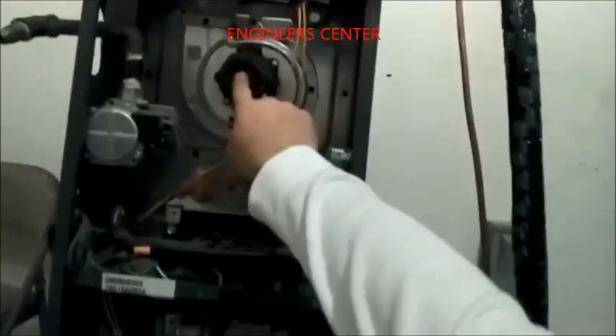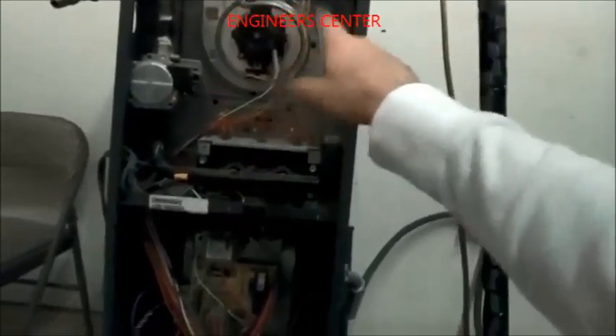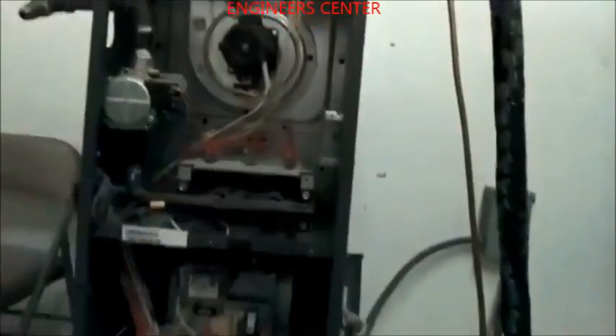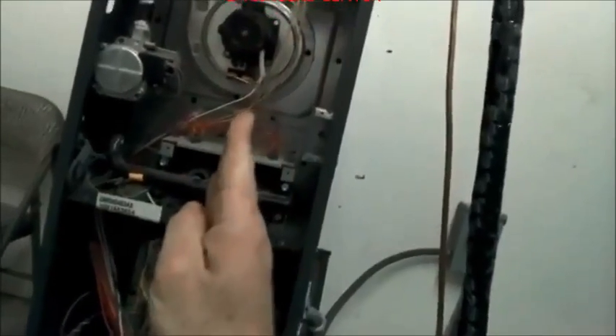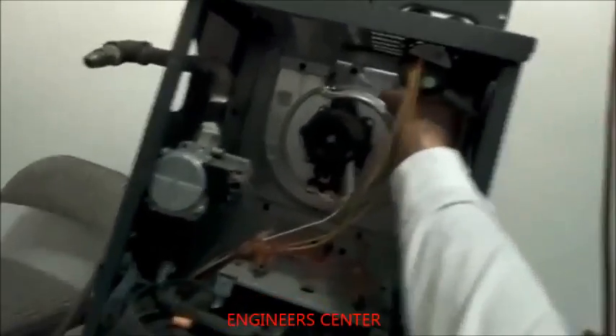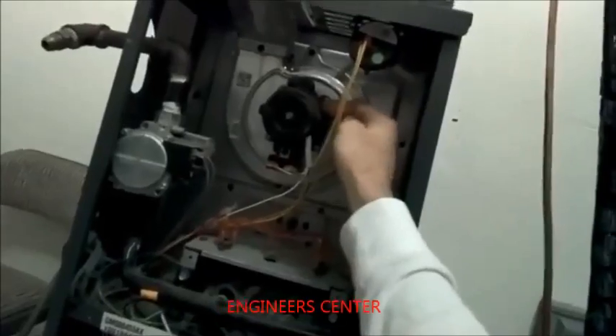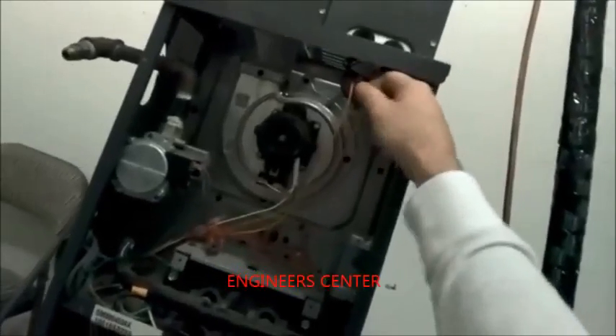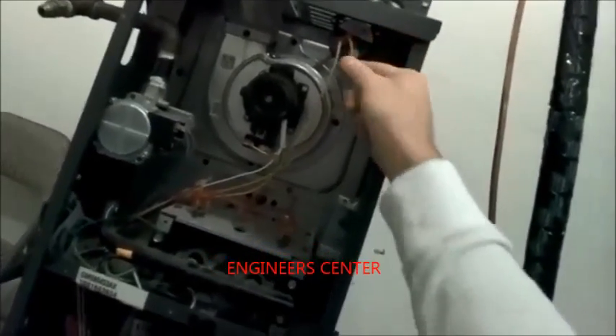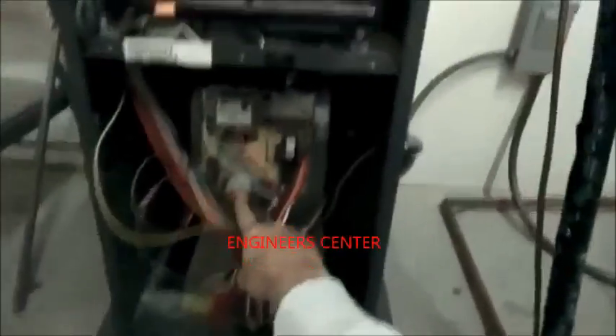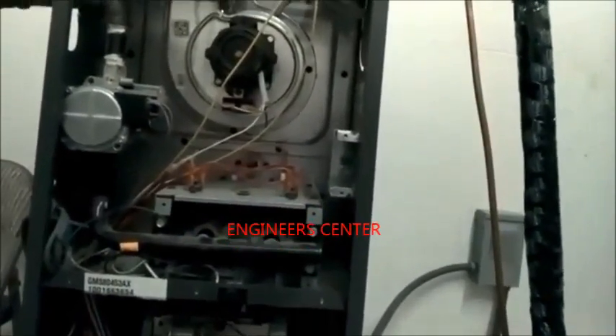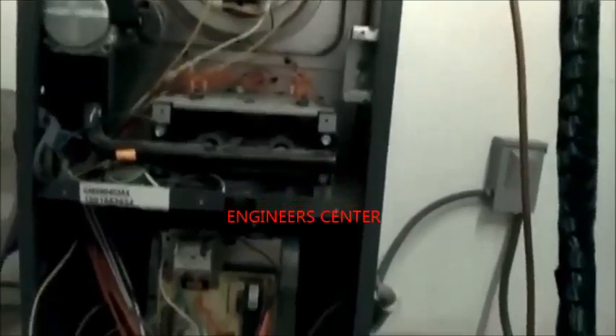And what we should see first is this inducer motor should come on and remove all the toxic gases and blow them out to flue. So that happens first. Once that happens, I know the next thing in sequence of operation is that the pressure switch here is going to sense the pressure being pulled through the tube from the inducer motor being on. And what it's going to do is it's the relay, like we said, so it's going to close. And so one side here is going to be energized at all times, and when the pressure switch closes, it's going to send that power back through this wire down here to the circuit board. And that's going to tell the circuit board, yep, the pressure switch is closed. That means the inducer motor's on. That means it's safe to light the gas.